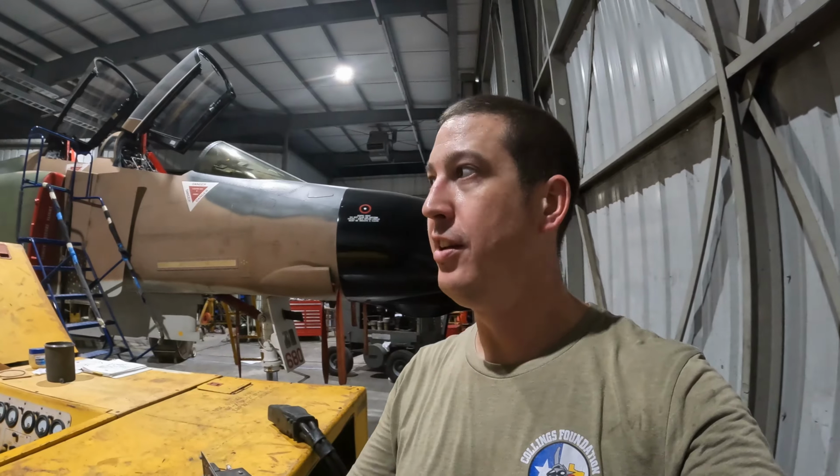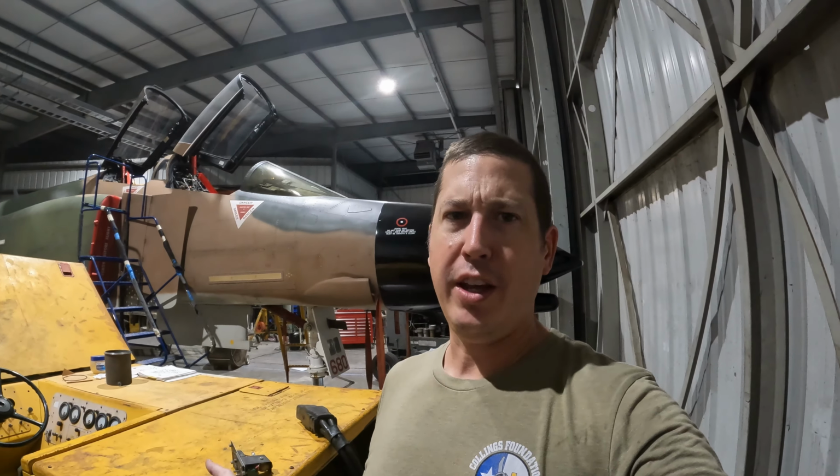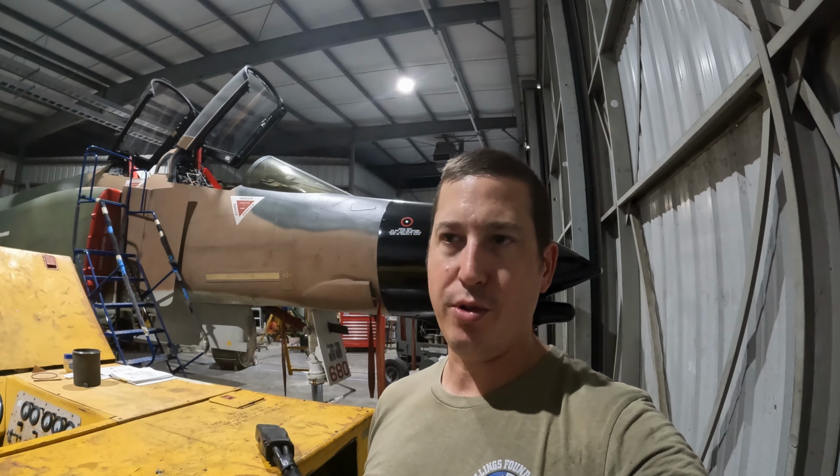together. Now, if you remember earlier, generators, especially AC power, has to maintain a constant speed in order to function properly. That's what keeps the frequency locked. And since the jet engine goes from idle speed to full speed, you can't direct drive a generator that way. So how does the generator maintain a constant speed? Well, there's such a device called a constant speed drive.